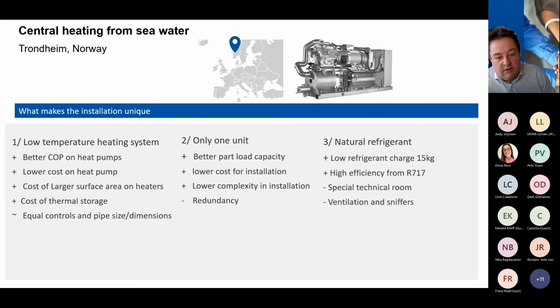1 unit is of course troublesome on redundancy if it fails, but here there's a backup system. But the positive thing about having only 1 unit is you achieve a better part load efficiency, and that can sound strange, but I will cover that topic as well. Lower cost for installation: you only have 1 set of pipes, 1 set of electrical cables, and you also have a significantly lower complexity in your system.